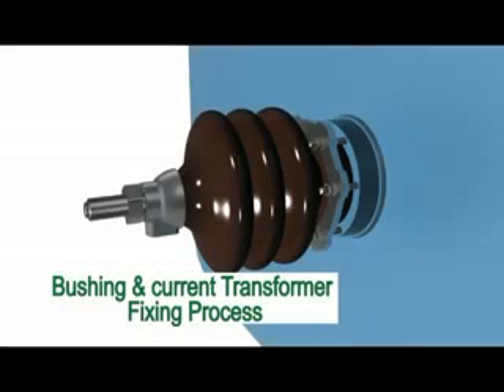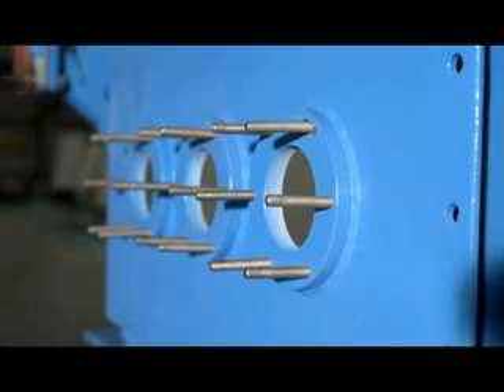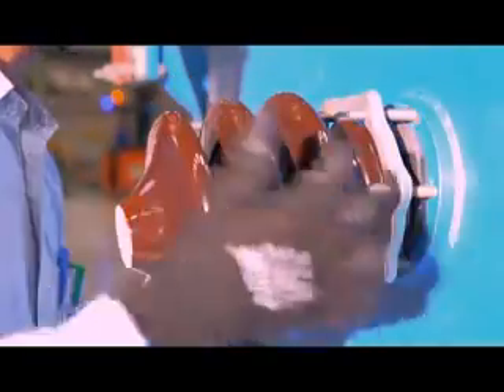Bushing and current transformers. Bushings for voltage less than or equal to 36 kV class are porcelain bushings, but based on customer requirements, these can also be of the OIP type. For voltages above 36 kV, these are the OIP type, oil impregnated paper.